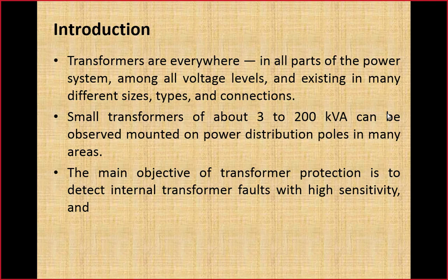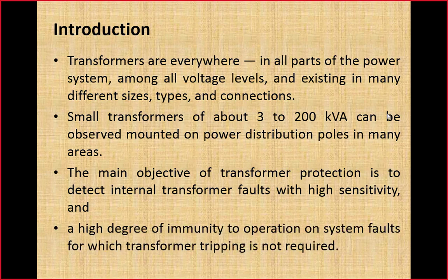Here is what we want from the transformer protection. Transformer protection should be highly sensitive so that it could detect all the faults within the transformer, or those faults which could affect the transformer. At the same time, transformer protection must be immune to the faults which are outside the transformer. So these are the two requirements. It should be highly dependable: all the faults within the transformer or those faults which could directly affect the transformer should be detected. And secondly, it should be secure as well, meaning all the faults outside the transformer must not be detected by these relays.